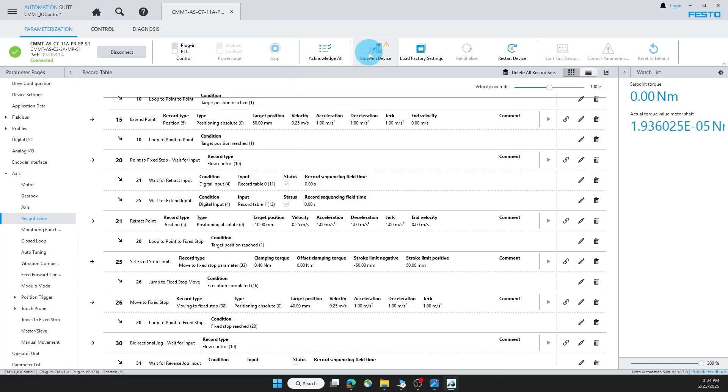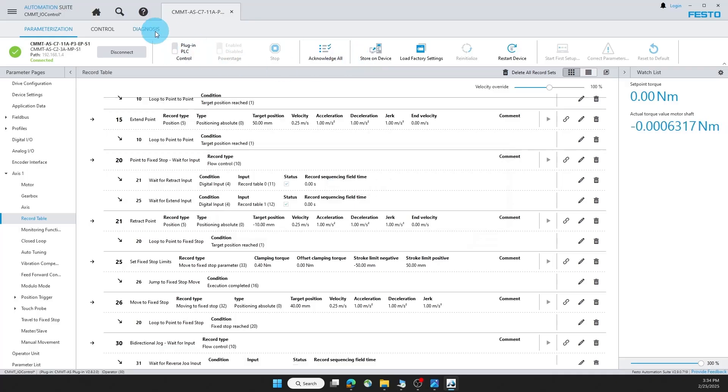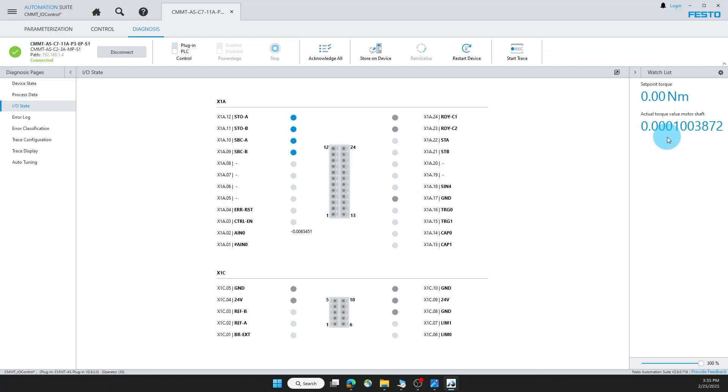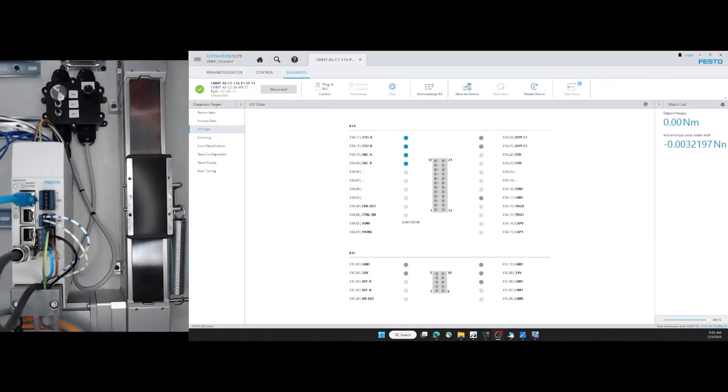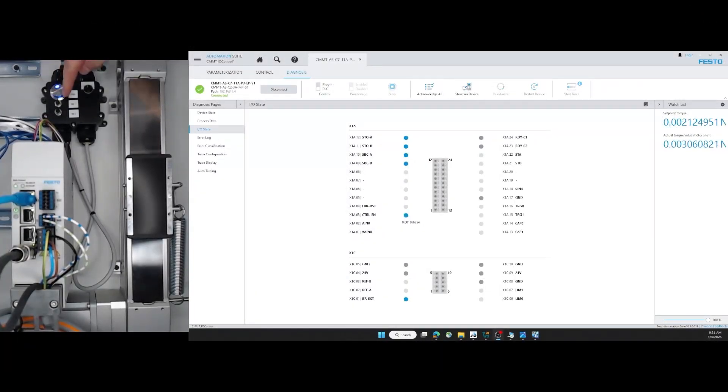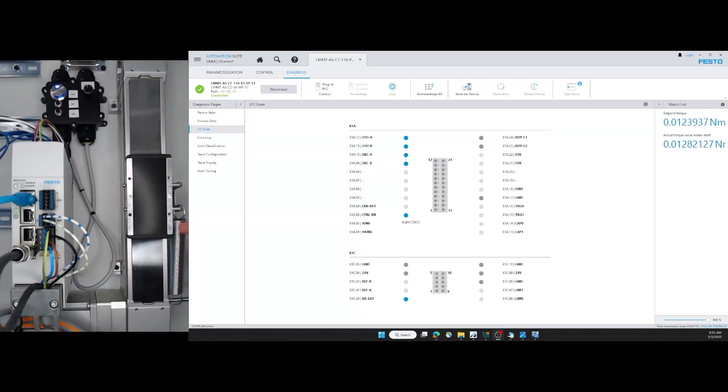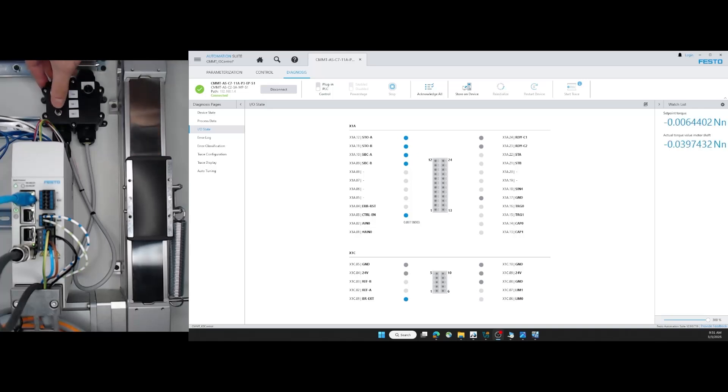Now I can store this on the device. Go back to diagnosis so I can view the inputs here. And you'll also notice the current torque being exerted here. Turn the motor on. And I have an input for my retract to a point, and then input for my extend to a fixed stop. Notice the spring I have here. This will not reach the full 40 millimeter stroke and it will reach the maximum torque due to this spring. Retract. Extend.